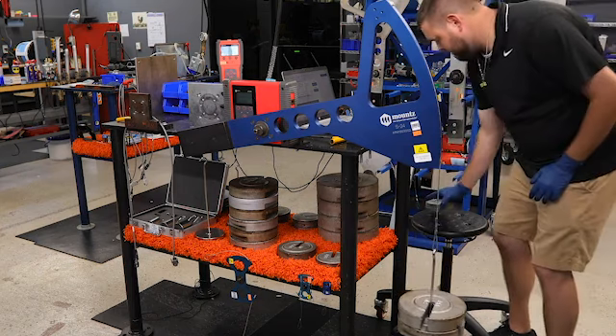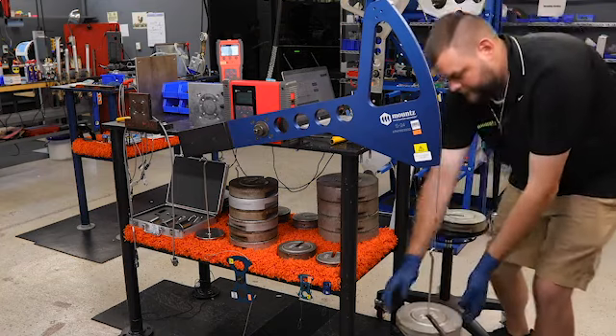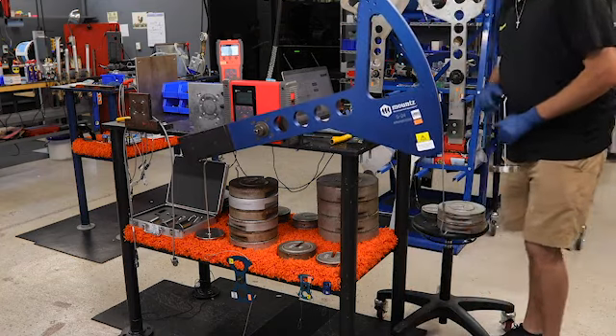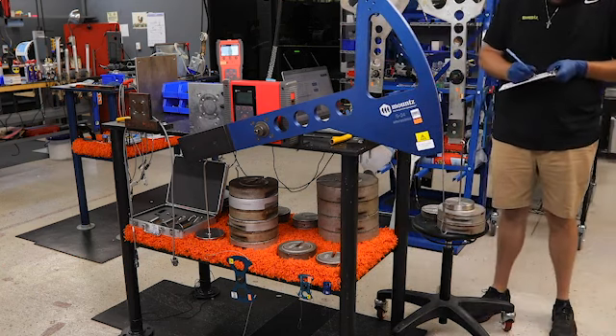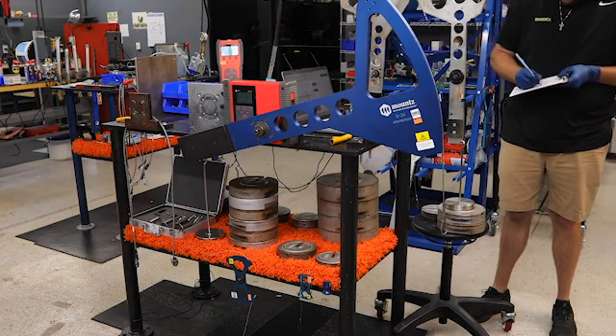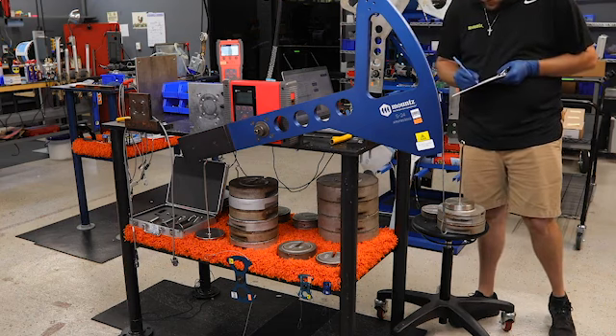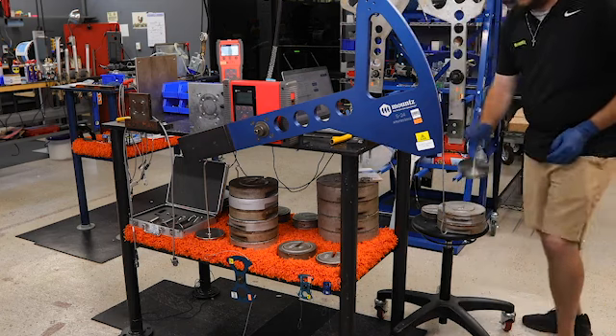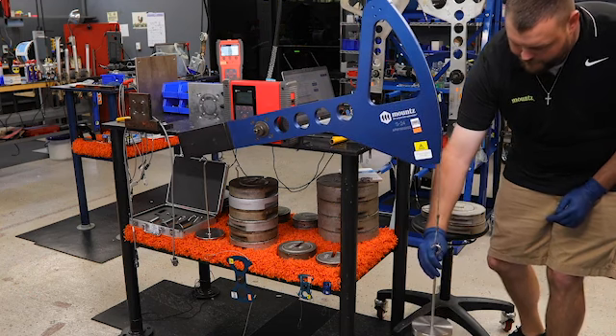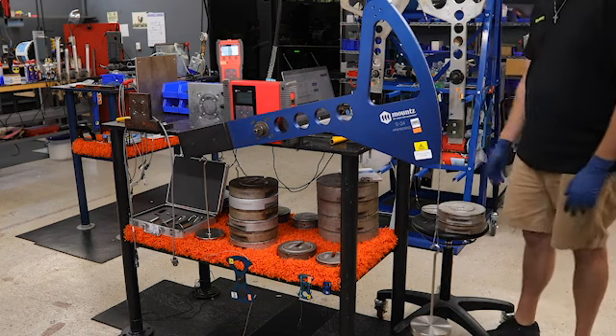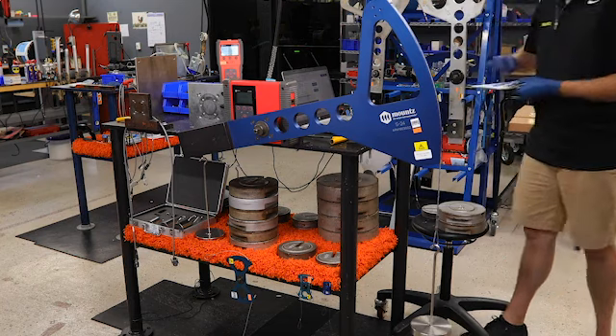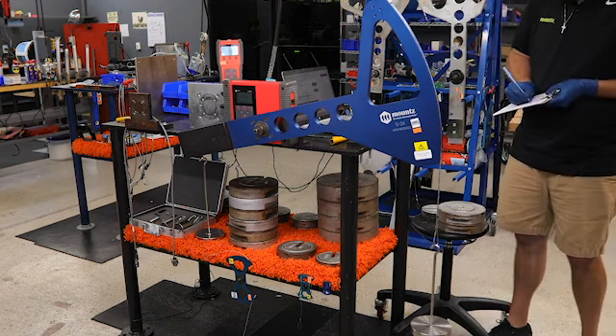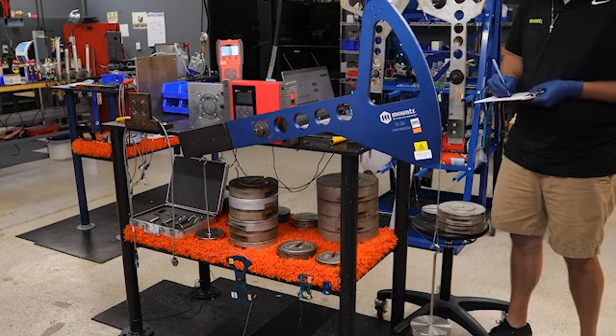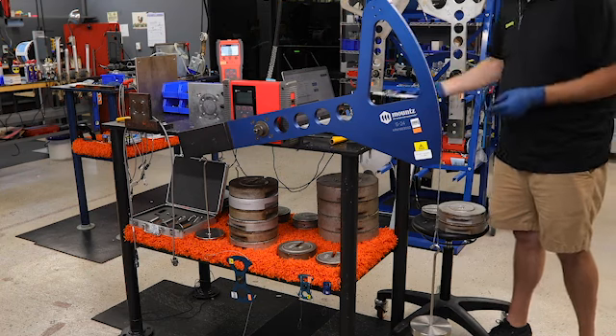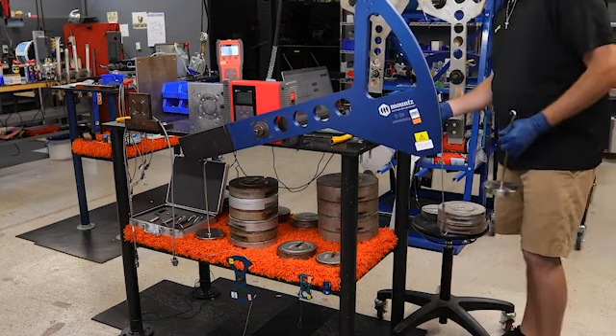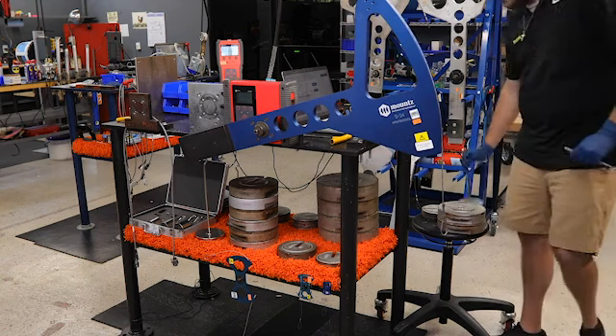So I have cut out the actual waiting part, so we're not sitting here waiting for that to happen during the calibration process. And as we begin the actual calibration process, again, we're going to start at 10%. So we will use the hanger and a 5-pound weight to get us to our 10-pound value. And as you can see, the weights are put on very gently and they remain still, so we don't get any variation in the torsion that may be happening during the process. And then that value is stored in the system. And then we'll move on to the 50% value.